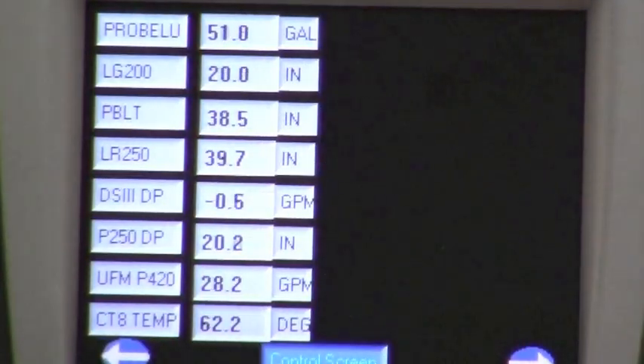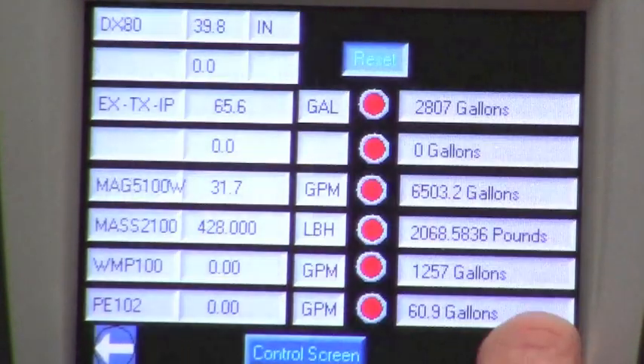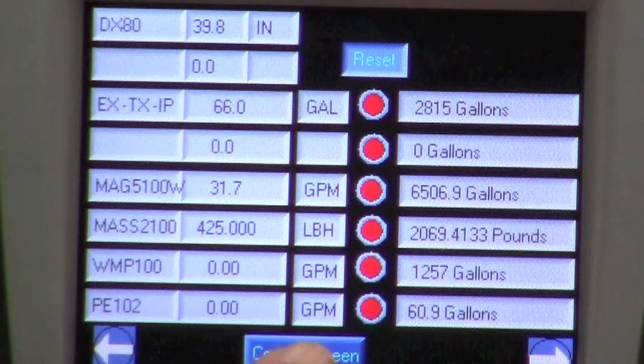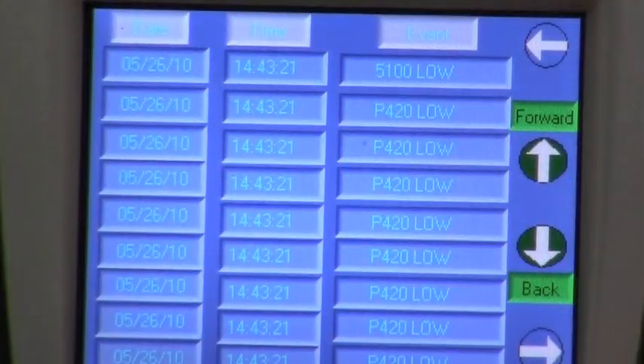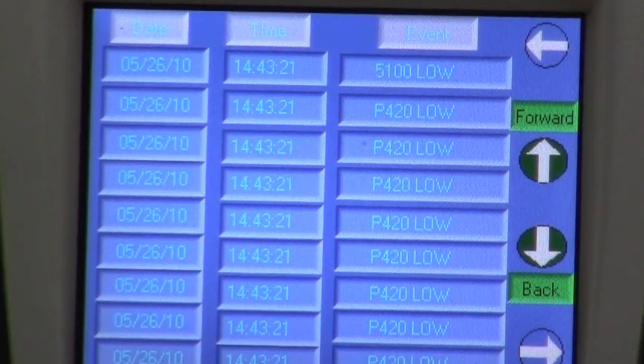Moving to the second display, this is a straight digital display. Third one — this is a flow display. On this one we're just showing the flow rate along with the engineering units and the gallons. We also have a touch screen here, so we can hit this and zero it out on the totalizer. Here's an event log — basically if you have any alarms it'll give you a tag along with the date and time associated with that alarm.